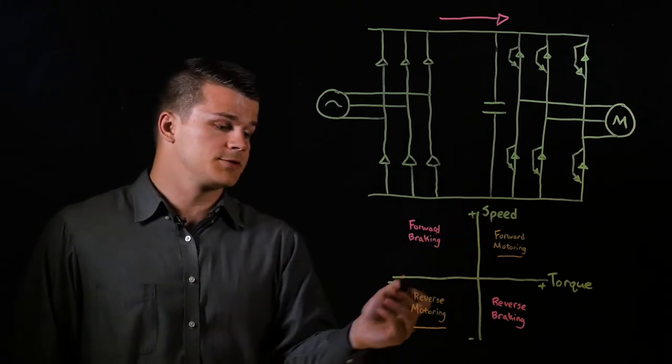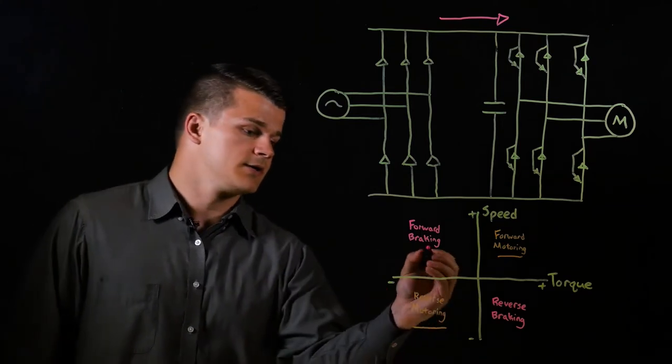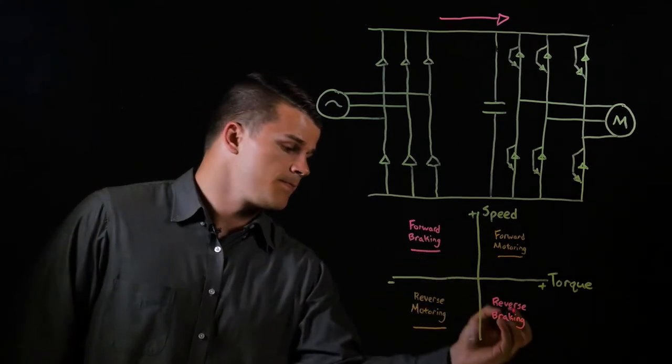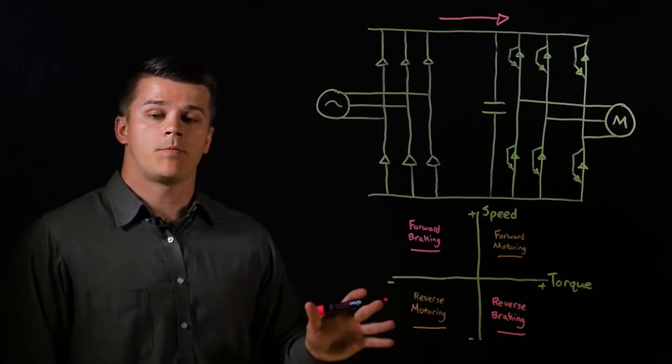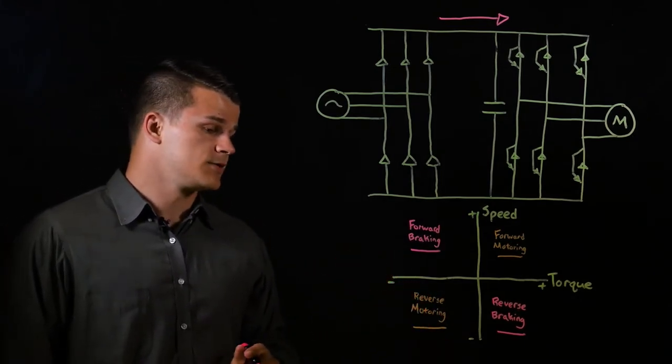If the speed of the motor is in the opposite direction of the torque applied, it's in a generating operation and takes a mechanical input of energy at the motor shaft and produces an output of electrical energy back towards the VFD.